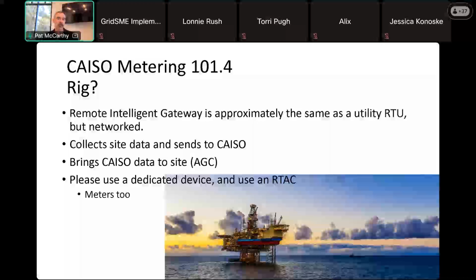So a rig is a remote intelligent gateway. It is approximately an RTU, except in terms of how it interfaces with CAISO, it's not a serial connection - that's an RTU. It's an Ethernet type connection, or it communicates over an Ethernet type data path. So it's networked. Also, locally or behind on your facility, there's typically a lot more networked traffic into a rig than there is into an RTU. That's more about compliance and convenience than anything else.